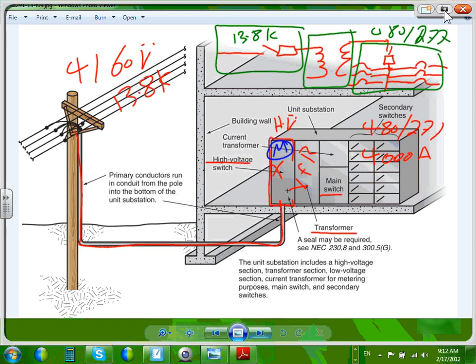Phil, depending on where you put your service point, they call it service point, the contractor, this could be service entrance conductor, meaning it's owned and operated by you, or it could be underground service lateral. Service lateral, meaning it's owned and operated by the utility. Very, very important term. So if this is my service point right here, not commonly used, then this will be service entrance conductor.